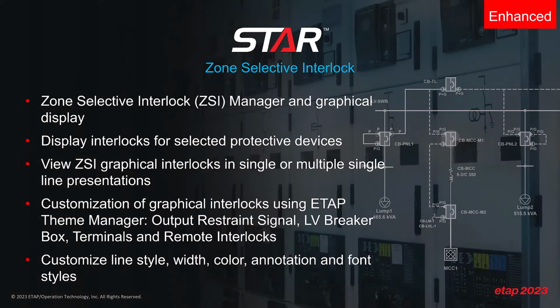Now, zone selective interlock has already been present in ETAP for the previous releases, and the ZSI in ETAP 2023 is enhanced so that you can see the ZSI graphically. You can display the interlocks for the selective protected devices. You can see the interlocks in either a single or multiple single line diagrams. You can also customize the look and feel of the interlocks using the theme manager, where you can customize the output restraint signal, the remote interlocks, the terminals, in terms of the line style, width, color, fonts, etc.